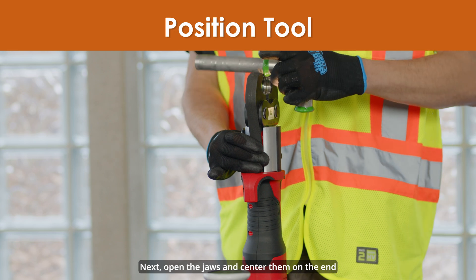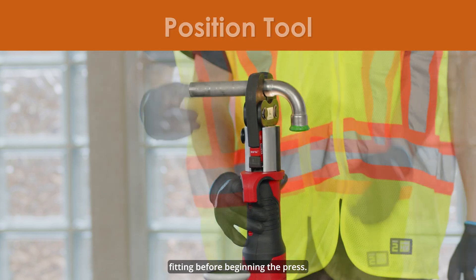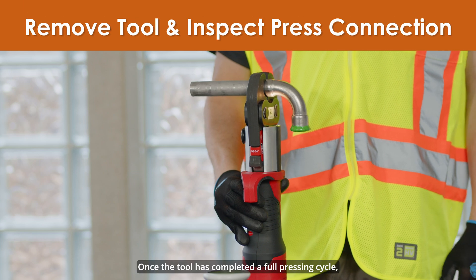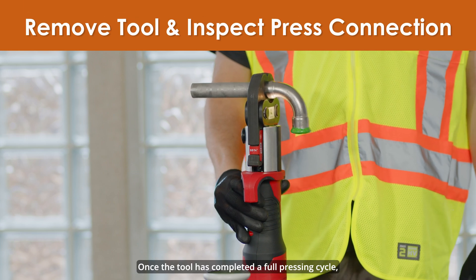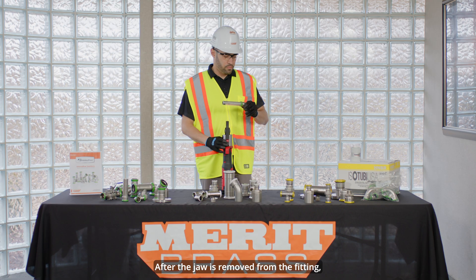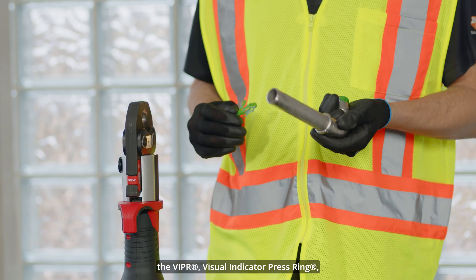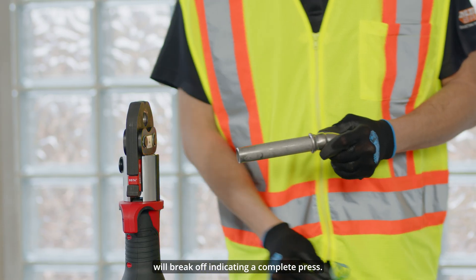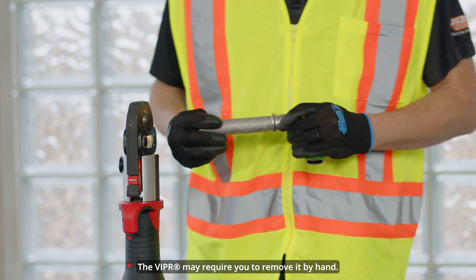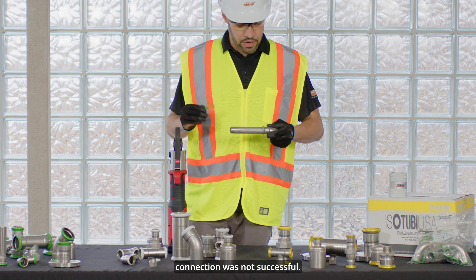Next, open the jaws and center them on the end of the stainless press fitting before beginning the press. Once the tool has completed a full pressing cycle, release the trigger and remove the jaw from the fitting. After the jaw is removed from the fitting, the VIPR, Visual Indicator Press Ring, will break off indicating a complete press. The VIPR may require you to remove it by hand — this does not mean that the connection was not successful.